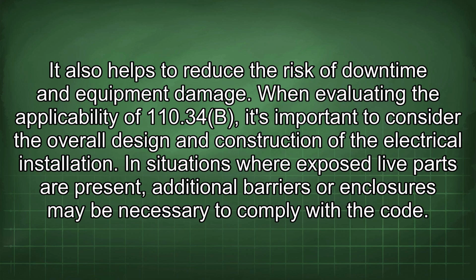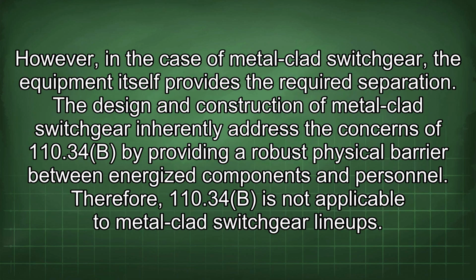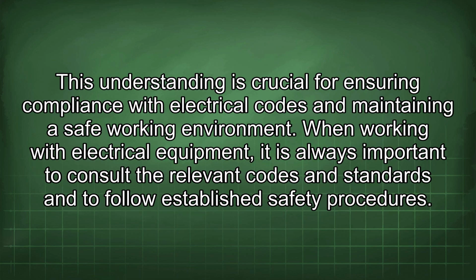When evaluating the applicability of 110.34b, it's important to consider the overall design and construction of the electrical installation. In situations where exposed live parts are present, additional barriers or enclosures may be necessary to comply with the code. However, in the case of metal-clad switchgear, the equipment itself provides the required separation. The design and construction of metal-clad switchgear inherently address the concerns of 110.34b by providing a robust physical barrier between energized components and personnel. Therefore, 110.34b is not applicable to metal-clad switchgear lineups. This understanding is crucial for ensuring compliance with electrical codes and maintaining a safe working environment.